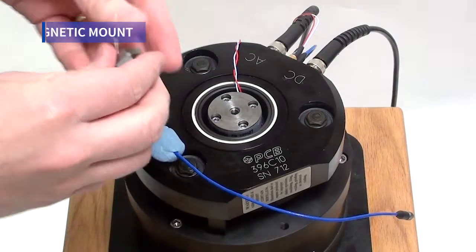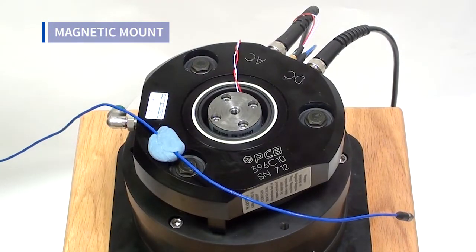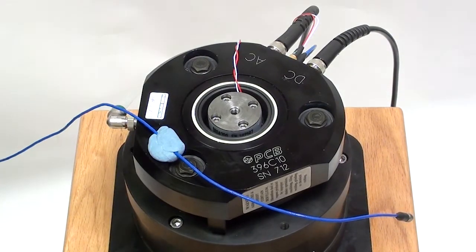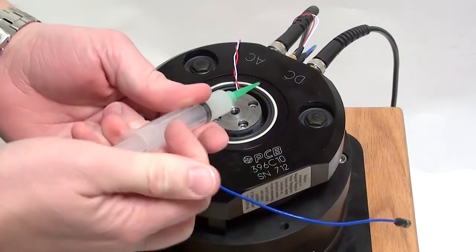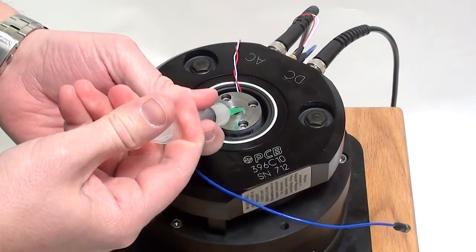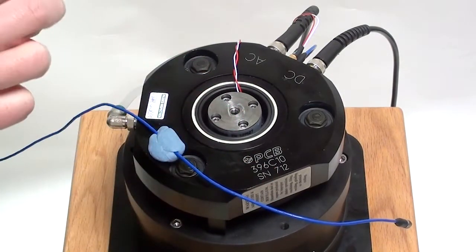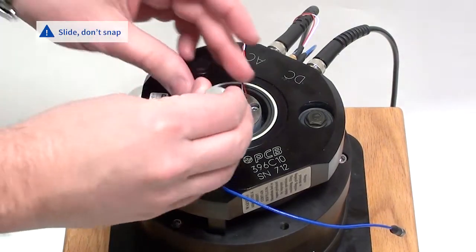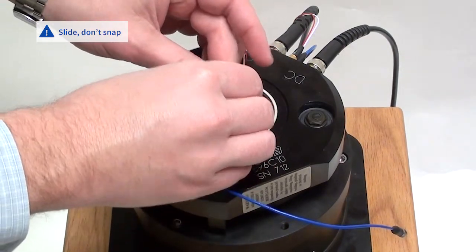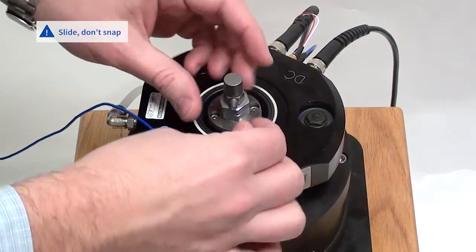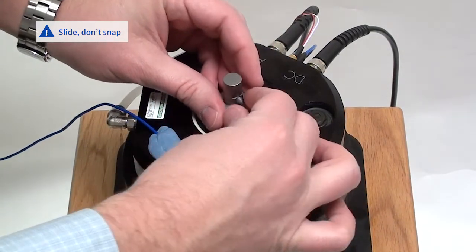The magnetic mount relies on a two-piece magnetic set, each of which is stud mounted to the mounting surfaces with the techniques noted previously. When connecting the magnets, take care to slide them together from the side and avoid snapping them together, which would damage the sensors.